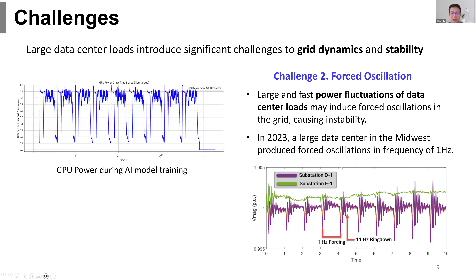In 2023, a large data center in the Midwest produced forced oscillations. This lower figure shows the field voltage in a substation, and we can see there was a 1 hertz forced oscillation in the voltage induced by the data center's power fluctuation.